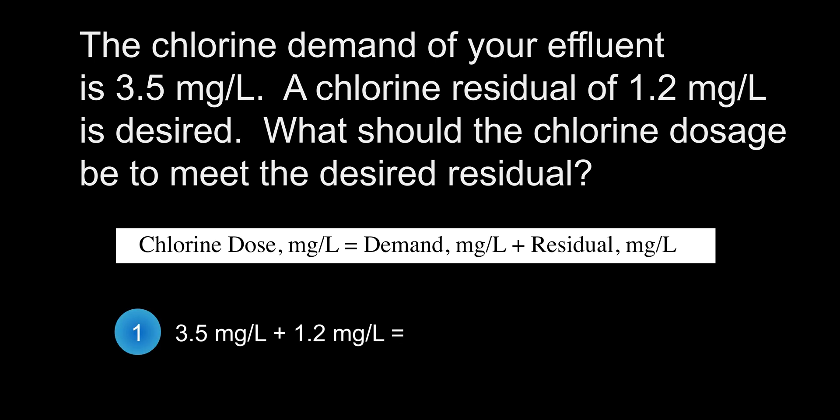We take the chlorine demand of 3.5 milligrams per liter and add it to the chlorine residual of 1.2 milligrams per liter to get a chlorine dose of 4.7 milligrams per liter. I have placed a link to an earlier video in this series — part 12, question 3 — that goes over chlorine disinfection in more detail.